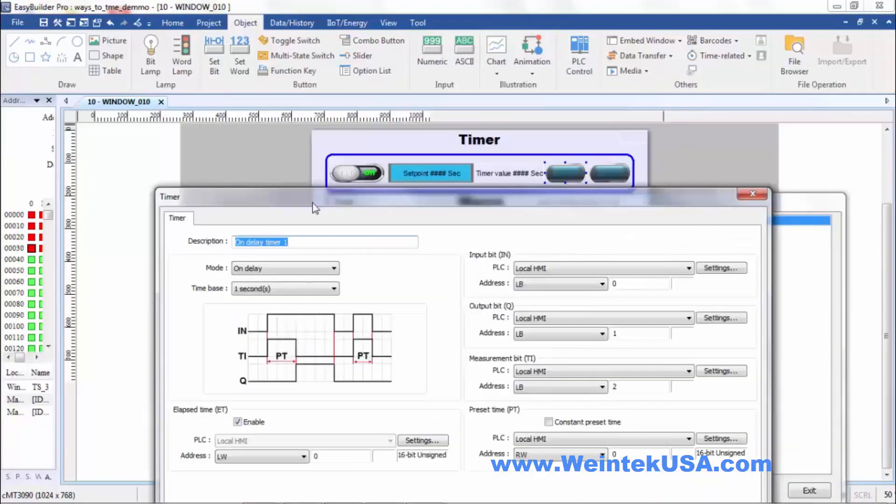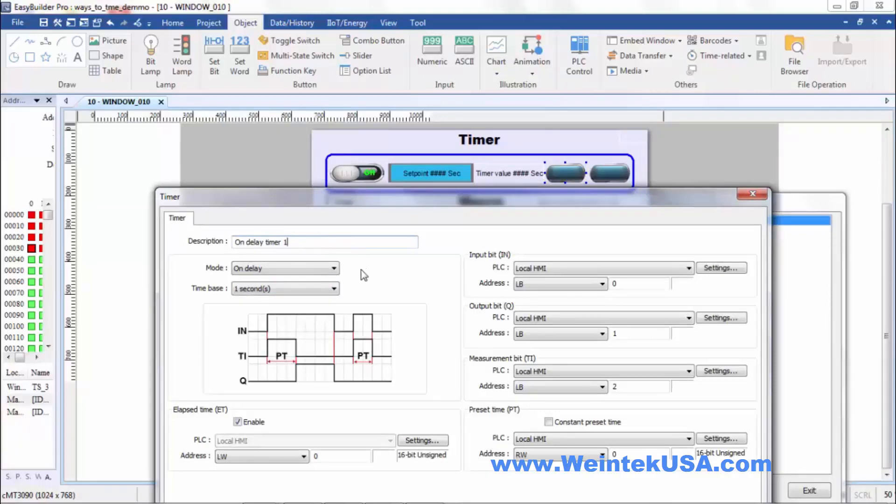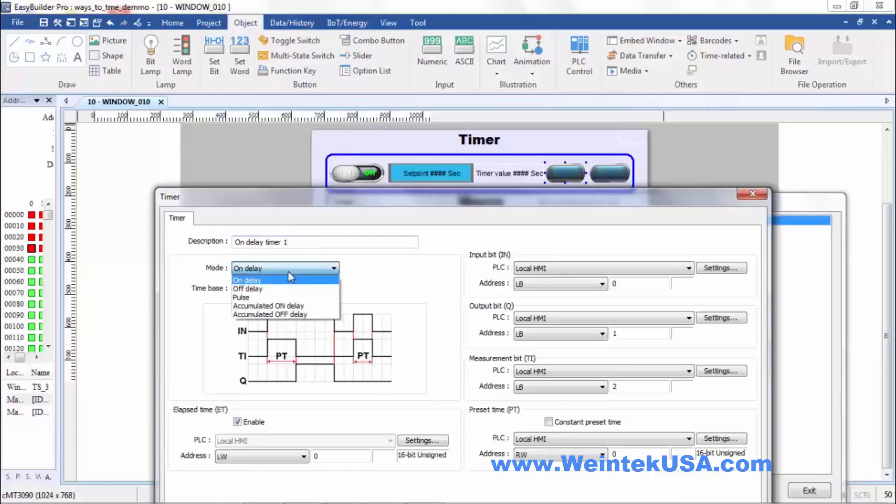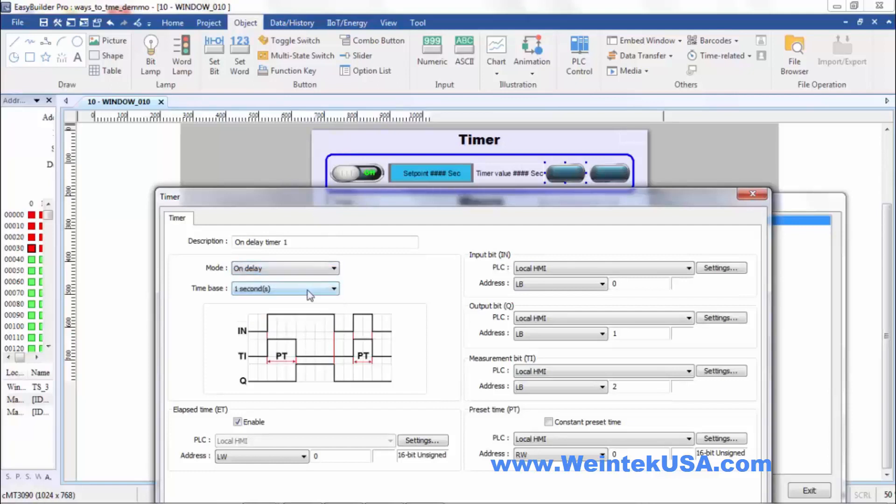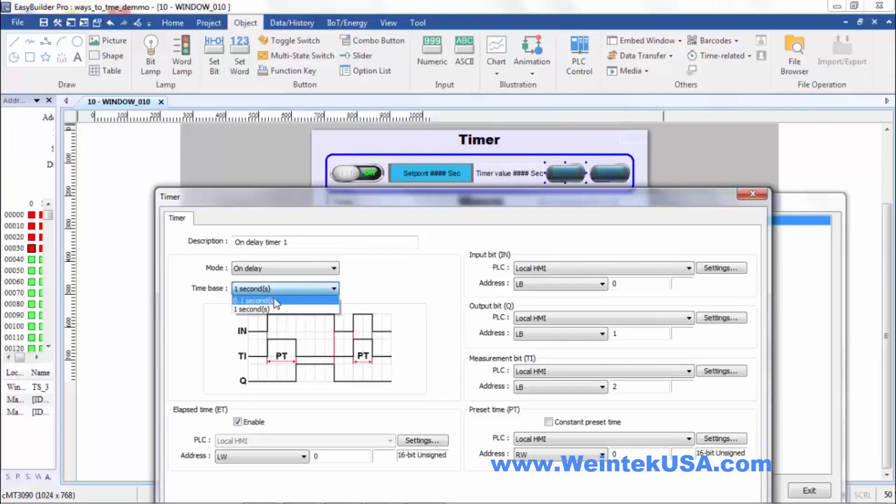Within this interface you can do a few things. You can actually name the timer. I called it on delay timer 1. You can choose the type of timer or the mode of the timer. I've chosen on delay. Your choices are also off delay, pulse, accumulated on or off delay. I've chosen a one second time base and you can also choose a point one second time base.